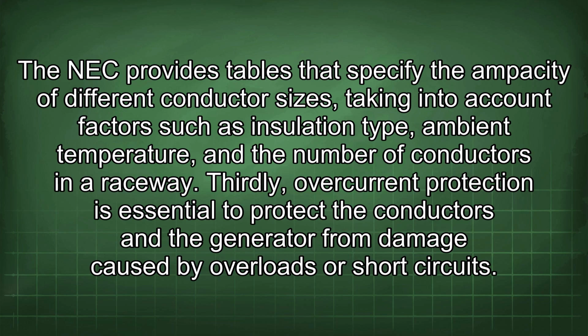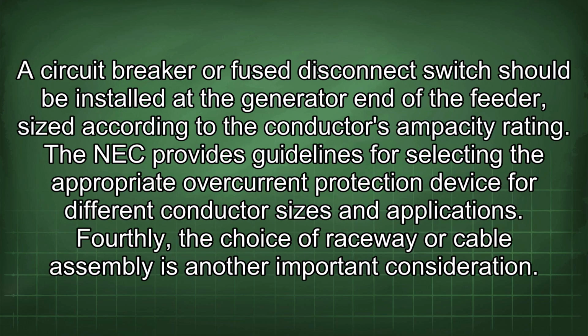Thirdly, overcurrent protection is essential to protect the conductors and the generator from damage caused by overloads or short circuits. A circuit breaker or fuse disconnect switch should be installed at the generator end of the feeder, sized according to the conductor's ampacity rating.